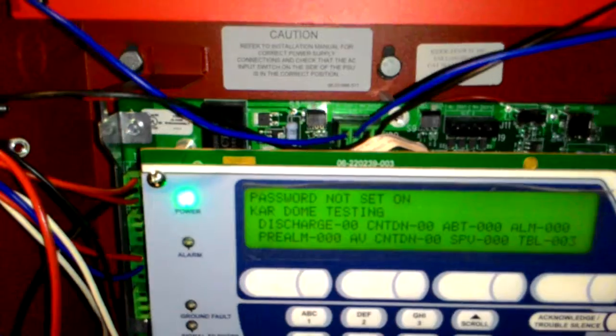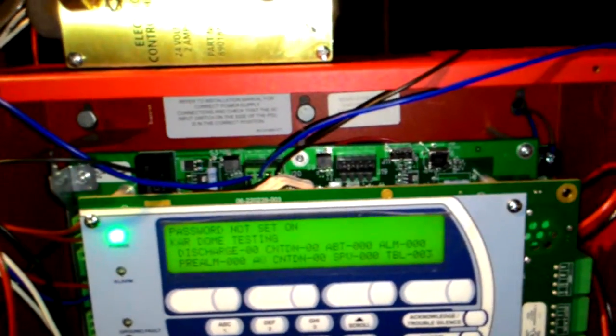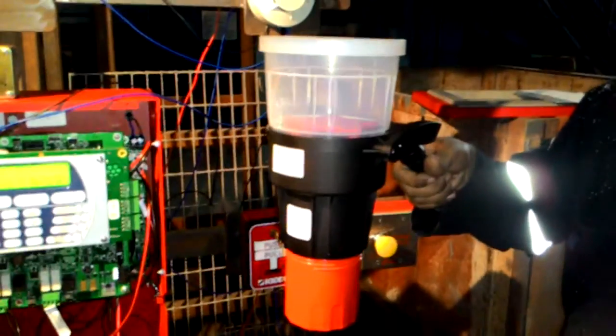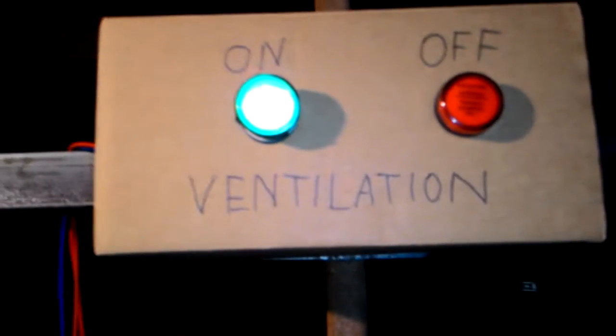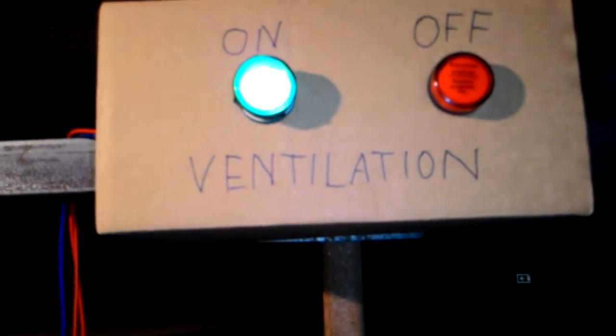Now we shall proceed with smoke detector's activation, which is done using a Solo smoke detector testing kit. Now, after the smoke detector is activated, the fire alarm or the fire strobe light should go on, and after a delay of 120 seconds there'll be a ventilation shutdown.